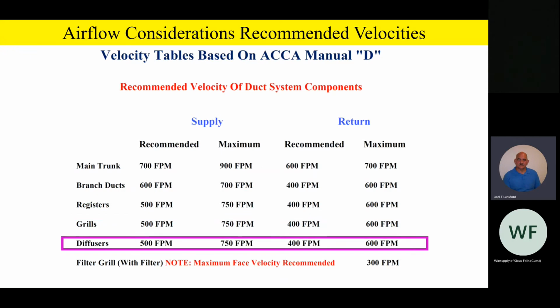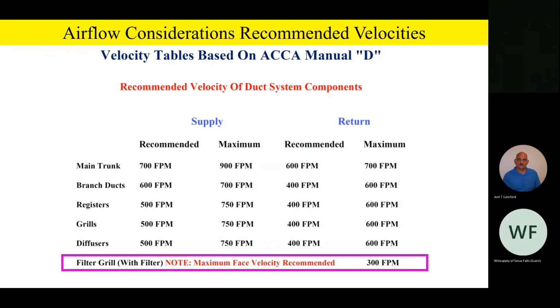Registers and grills and diffusers are all going to have recommended velocities and maximum velocities, and we always like to go with the recommended velocities. Now, one thing that's really, really important, depending on what area of the country you're in, you may have a filter grill or a return air grill with a filter in it. Well, if you do, please remember, Manual D recommends a maximum velocity going across that filter grill with a filter in it, not to exceed 300 feet a minute face velocity.